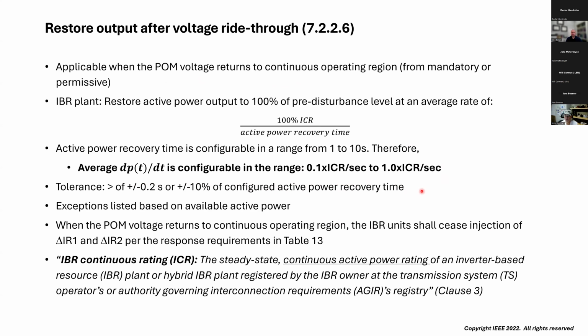And the standard gives some tolerance to that. I think one key thing to keep in mind is the requirement is not written as if you recover faster than this, you're fine. It needs to be at this average rate. It also talks about in this clause that any incremental reactive current that you injected during the low voltage ride through or high voltage ride through needs to cease or go back to pre-disturbance per our time domain requirements on the previous page, or in Table 13, I should say, two slides ago.